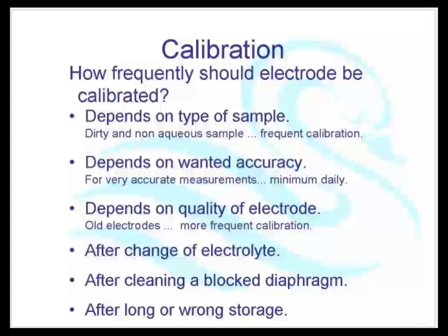I'm trying to find a polite way of telling you that it's a complete piece of rubbish. It's a dreadful, dreadful sensor. All pH sensors. Some are better than others, but basically they are all rubbish. From the moment the probe is made, it starts to deteriorate. It has a limited shelf life, and the older the glass gets, the more it drifts out of calibration.